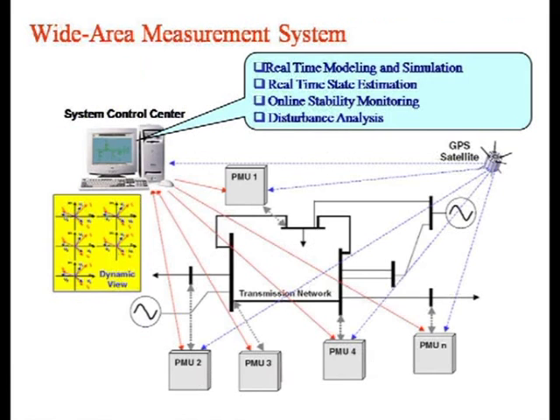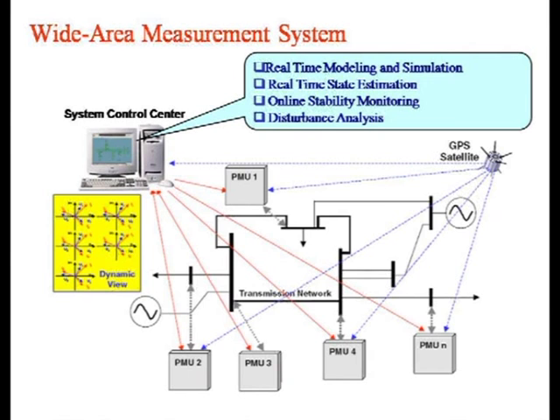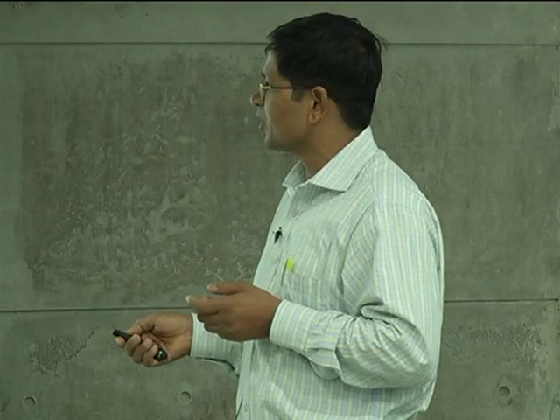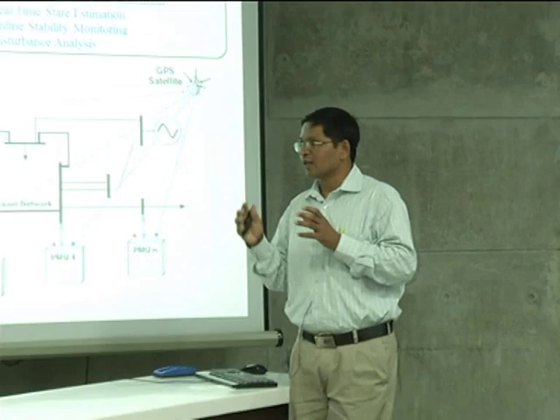We have an interconnected network — more or less like a ring network — with generators, bus bars, and some important lines. At some of the important bus bars we have the use of PMUs. These PMUs send information to a centralized control center, which will receive the phasor signals from all the bus bars. The PMUs send signals that are time-synchronized via GPS satellite to the center. With information from important bus bars available at the control center, we can have a sufficient level of monitoring in the interconnected systems and then apply the control strategy.